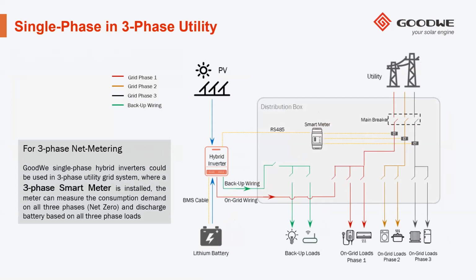So our single-phase inverters are capable of being installed in a three-phase utility. A separate three-phase smart meter can be purchased. This is generally for net metering. If a customer has net metering and can balance out his power by feeding back on one phase, this is a good option. So the three-phase smart meter will then detect all the loads on all three phases and then discharge the battery and use the PV to cover all the loads. So normally in this kind of configuration, you would have export on one phase and try to balance out in the net metering.